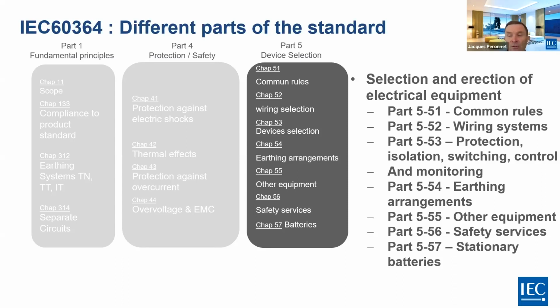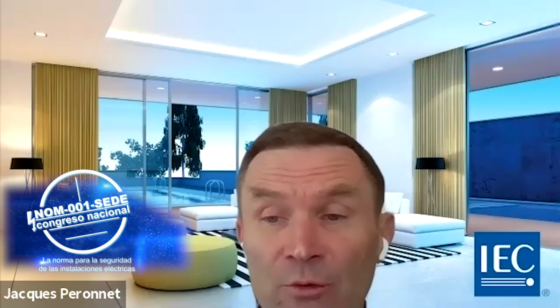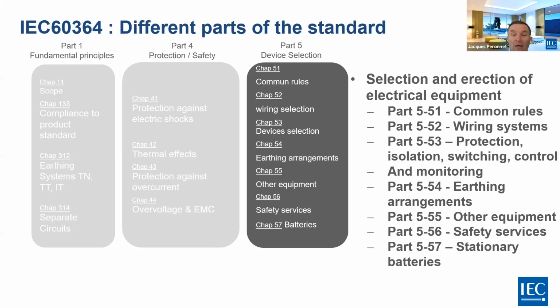So this is where we are going to select the wiring, which could be cable, but also trunking and so on. Everything is described. And you are going also to select, when you have the combination of different cables, how to install it correctly, and take into account the interaction between the different wiring systems. The part 53, which deals with the protection, isolation, switching, control, and monitoring. So this is really on this part where you are going to select all the devices you are going to install in your installation. Then you have a part 54, which is the earthing arrangement.